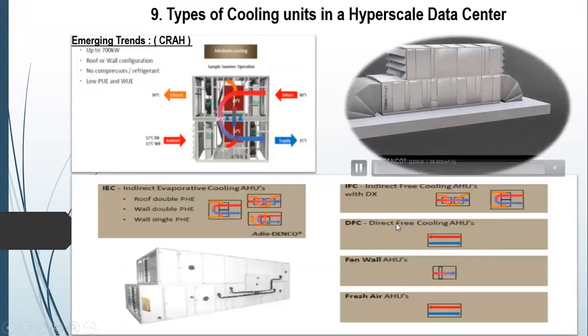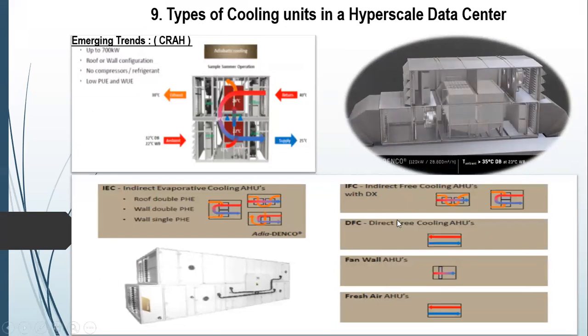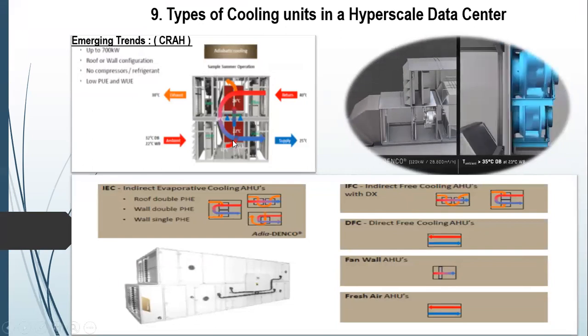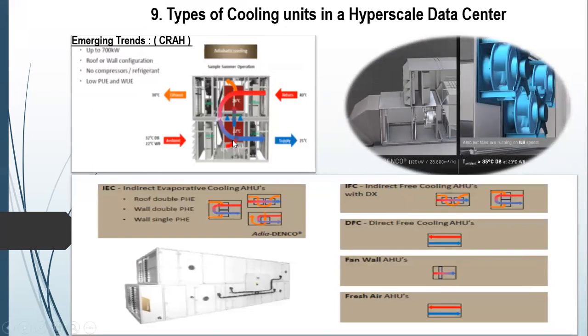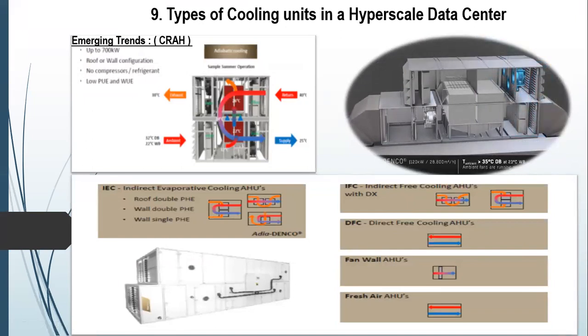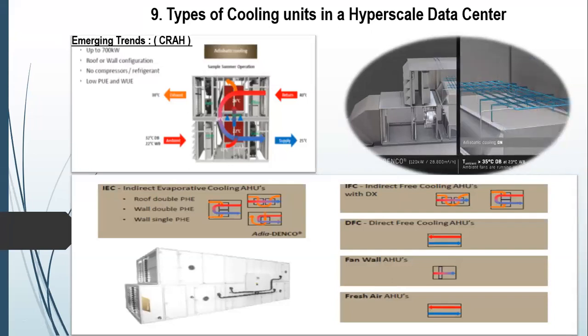So this is a video as a talk of an indirect evaporative cooling where the capacity goes up to 200, 300, 500 kilowatt, which are placed above the data center or on the same floor. Where we spoke on free cooling, where the direct air is taken into the server room. Here it is an indirect air where the outside air is not taken inside the server room. So we don't have the outside contaminated air entering the data center.